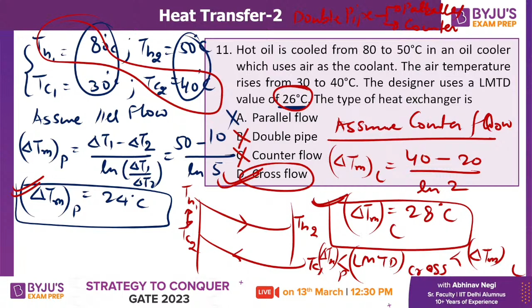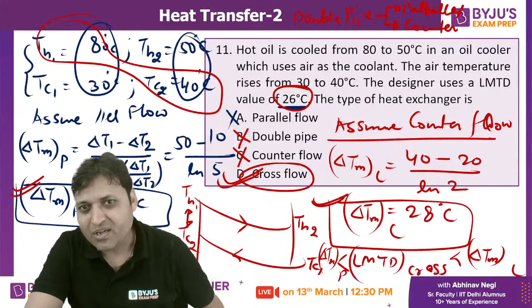If the designer value would have matched with parallel flow heat exchanger value, then the answer would have been parallel flow as well as double pipe. It could have been MSQ. If the parallel flow is the correct answer, then double pipe will also be correct. If the counterflow is the correct answer, then double pipe will also be correct. But because it is neither parallel nor counter, it cannot be a double pipe heat exchanger. It is complex heat exchanger, that is cross flow.